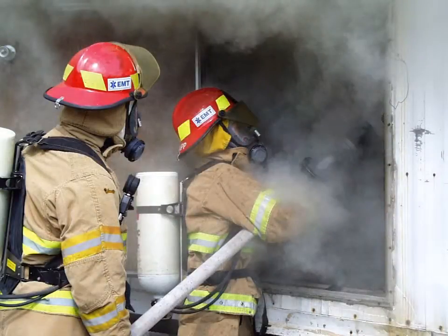When water from a fire stream is broken into small droplets, such as from a fog nozzle, it absorbs heat and converts to steam more quickly than in a compact form, such as from a solid bore nozzle. How much heat a fire stream absorbs is dependent on the surface area of water put into an area.